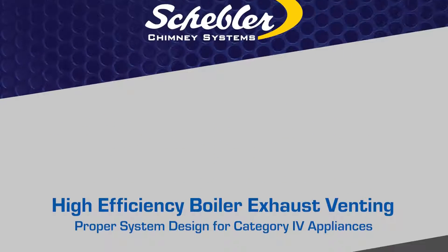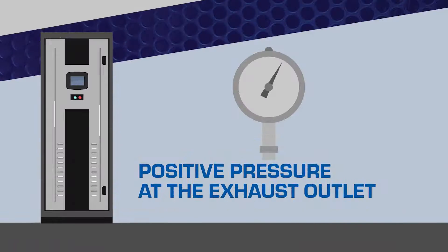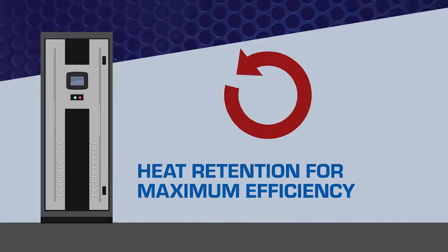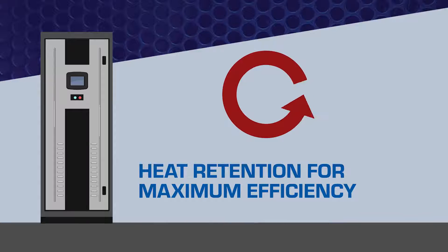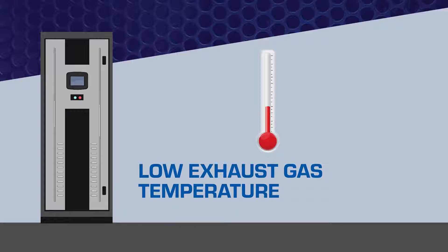Category 4 boilers and hot water heaters are designed to operate at a positive pressure exhaust outlet for heat retention, maximum efficiency, and flame stability. They are also designed to operate with low exhaust gas temperature — below the dew point — to allow the exhaust to condense inside the venting system.